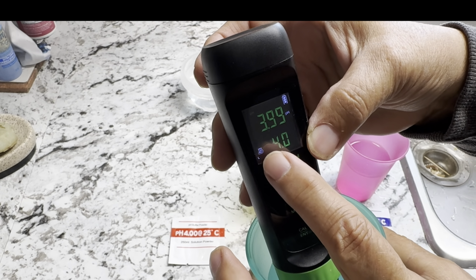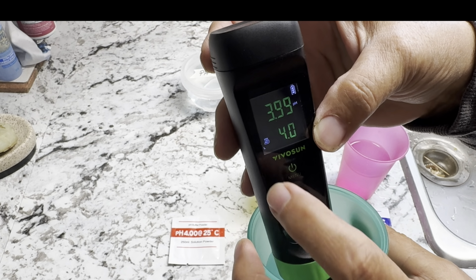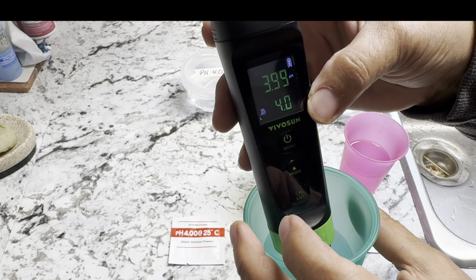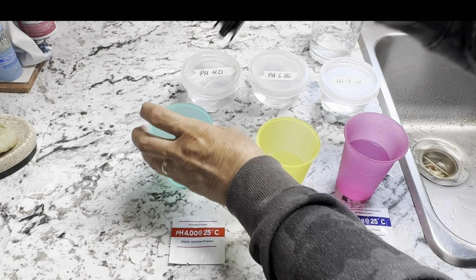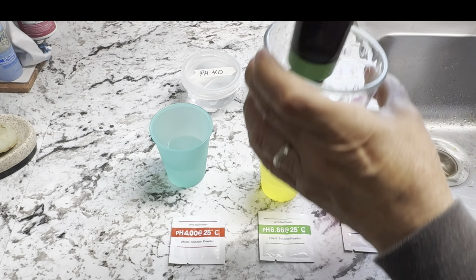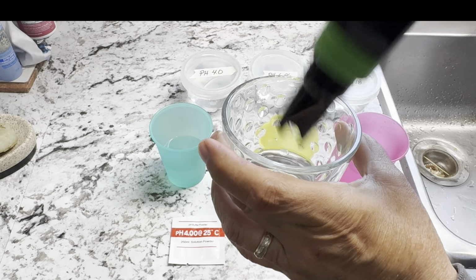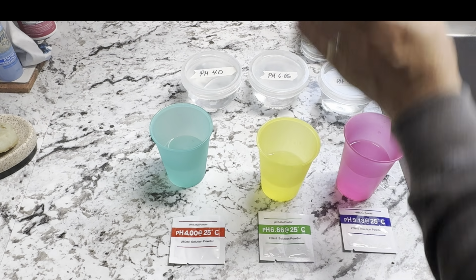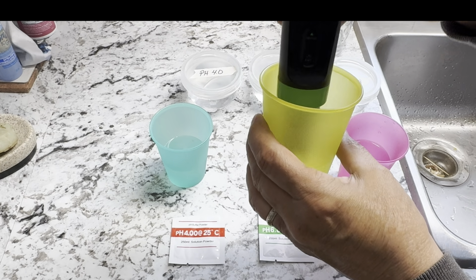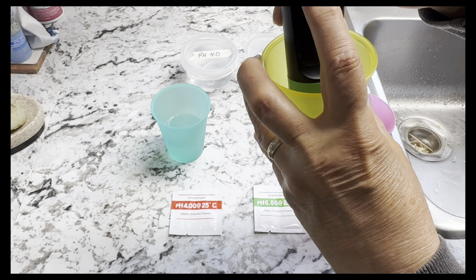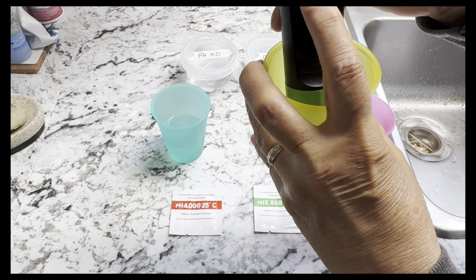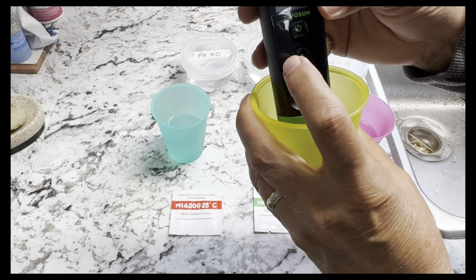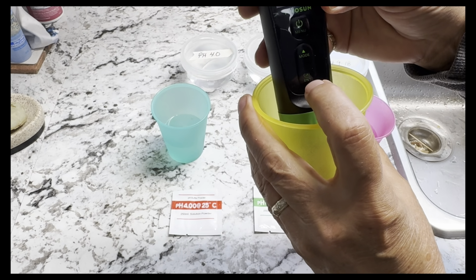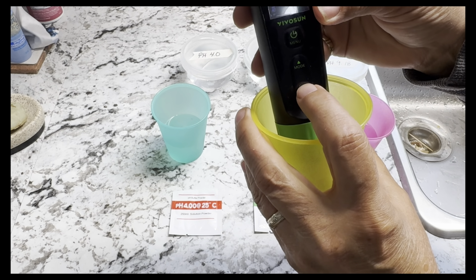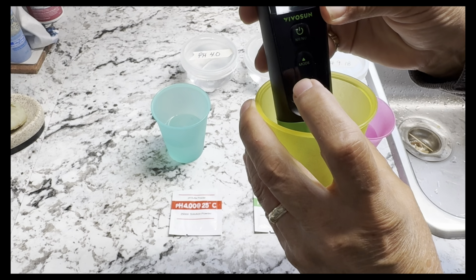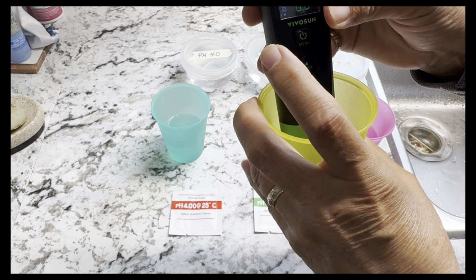A little tiny happy face will appear on there, and that will mean that you have calibrated it at the 4.0. Then you just want to give the probe a little rinse in some more distilled water, shake it off. You're ready to do the next one. Set it in there. An M will show up, and that flashing thing will go in the corner while it stabilizes. Once it stops flashing, hit the calibration button. A little happy face appears, and you're good to go at that level.